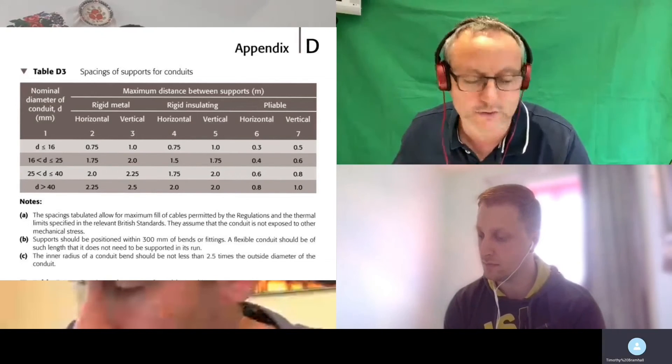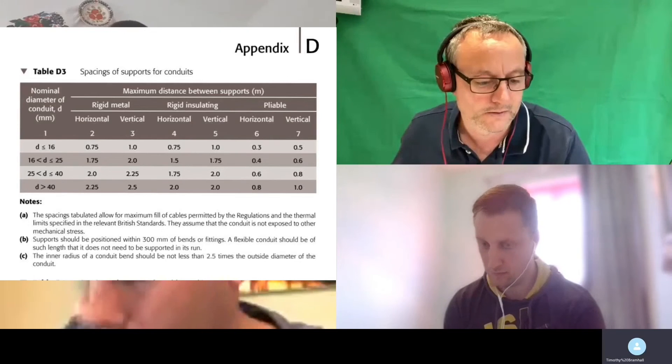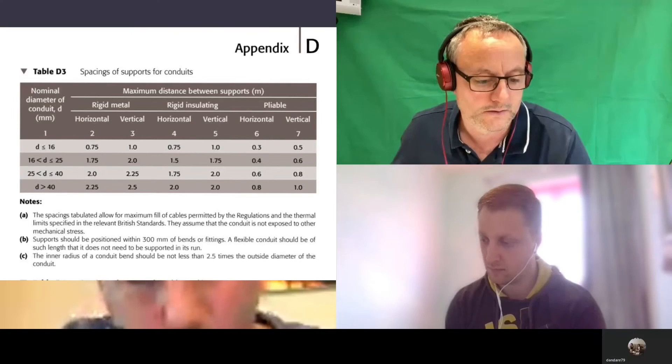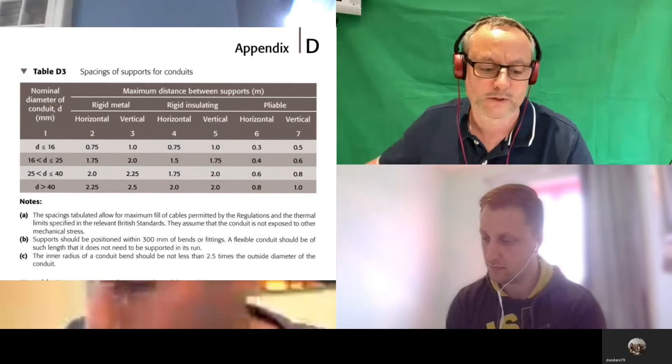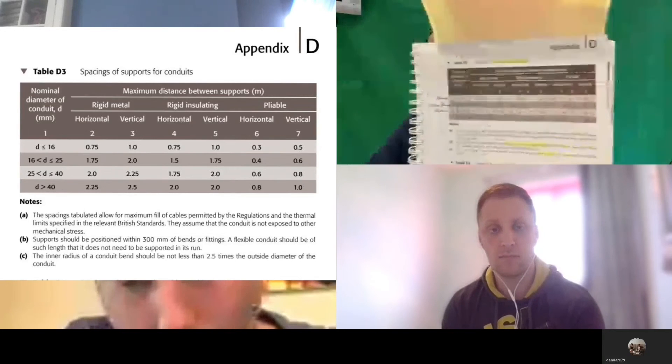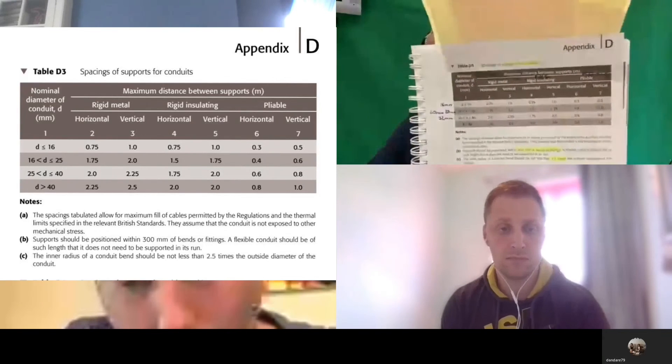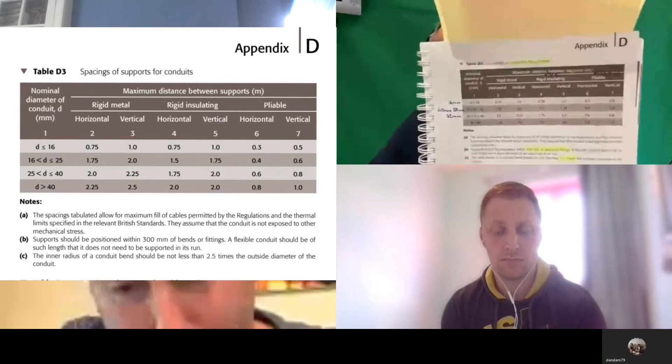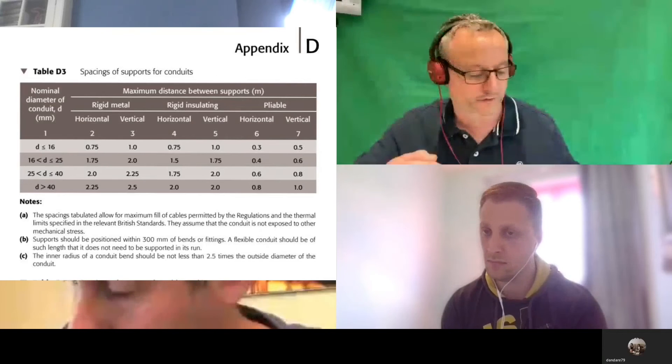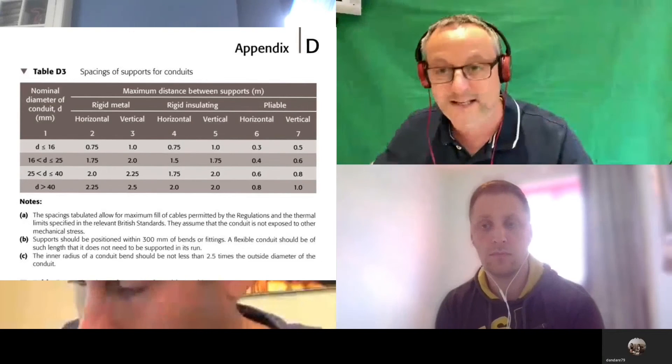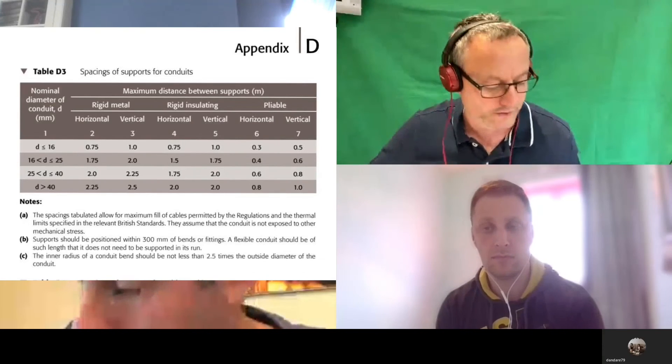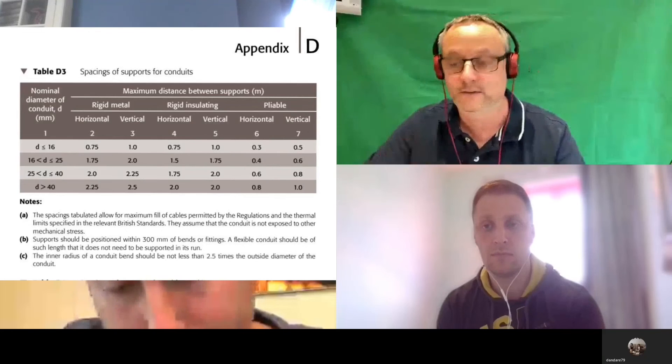Then if we go for Tim, what if we had a 32mm conduit? It's two meters horizontal and 2.25 vertical. Brilliant. So we've used columns one, two, and three in there to work it out for metal only. We could have gone on and looked at plastic and flexible if we wanted to as well. The notes only required us to do that, so brilliant, well done.